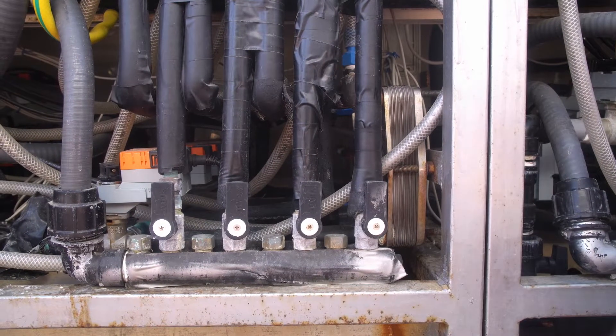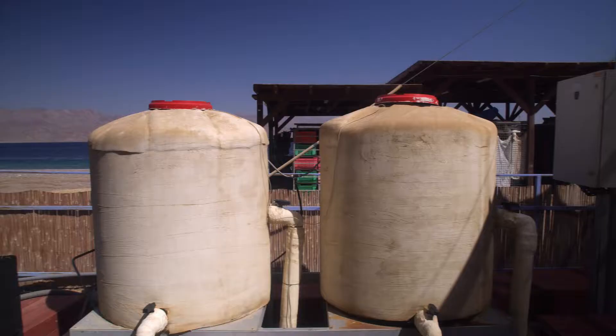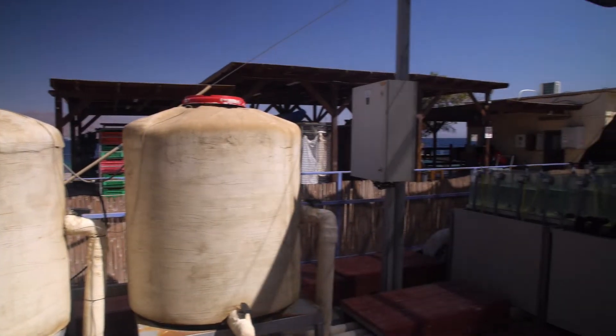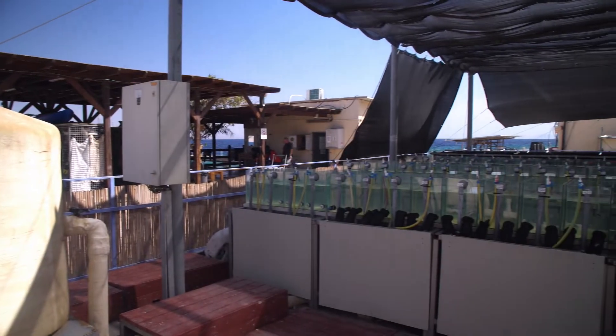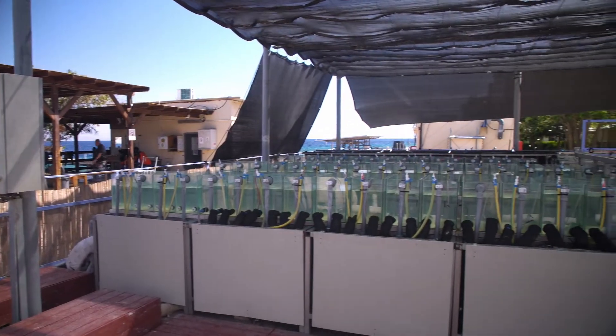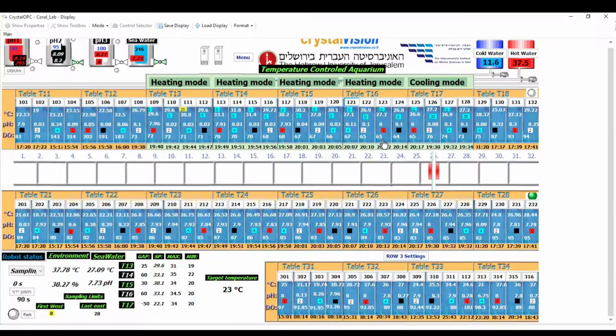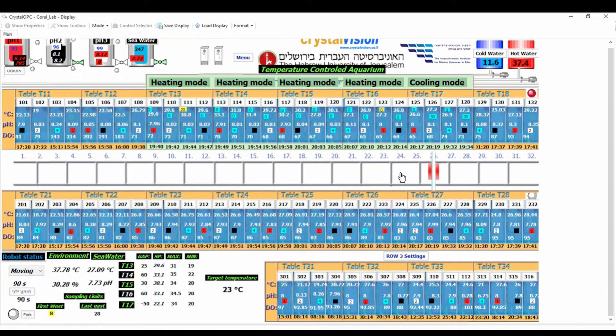Water is pumped through a titanium heat exchanger where it flows counter-current to adjusted quantities of hot or cold fresh water. In this way, the temperature is tightly manipulated. Temperature is typically set at a delta from the incoming reef seawater in order to maintain the diurnal variability.